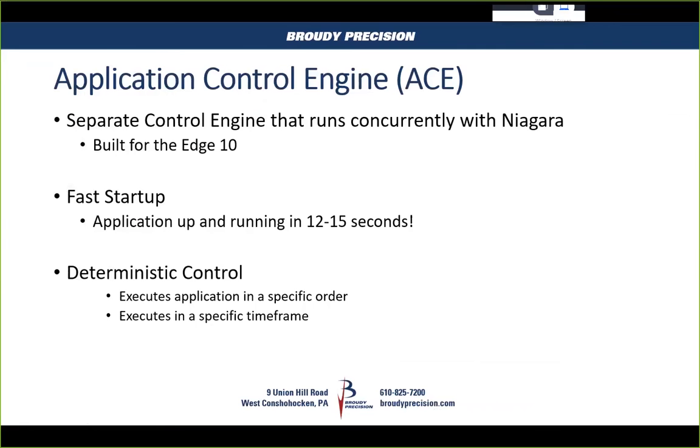The main thing with this is it's making it more like a regular DDC controller, where you apply power and it's up and running within 10, 20 seconds or whatever. It's also a deterministic control. So each component will execute in a specific order, and the cycle time is a specific time frame that it runs as well. So you know exactly what's going to happen when with that application.